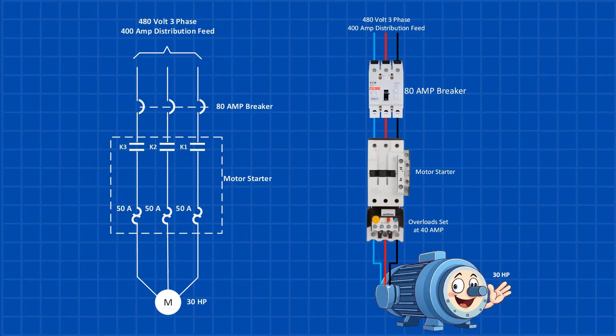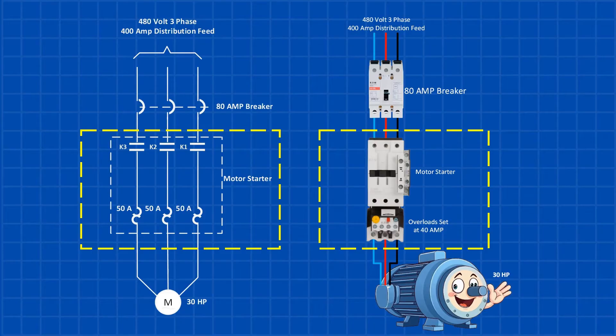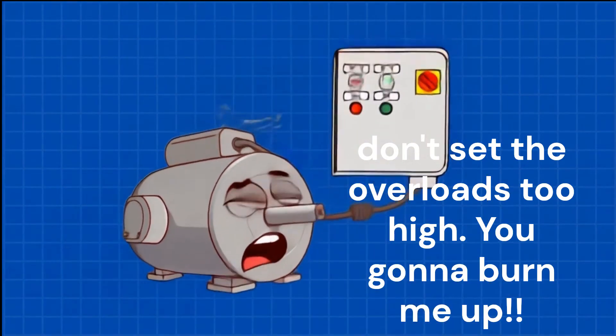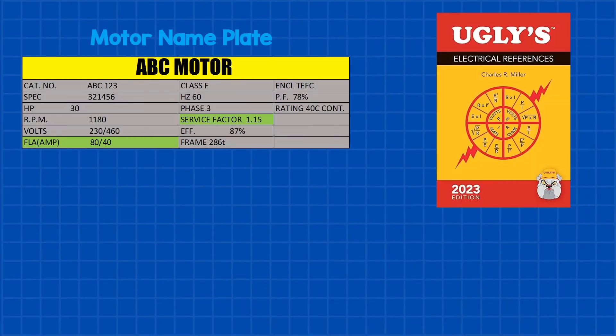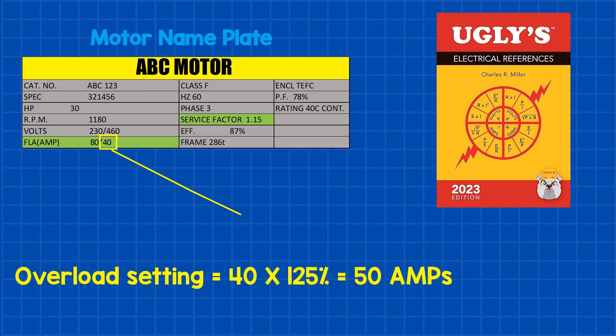To start a three-phase motor, all three phases need to be powered simultaneously, and that's where a motor starter comes into play. It has three contacts that close at the same time to send power to the motor. The motor starter also includes overload protection. If the motor draws too much current beyond the set limit, the overload protection trips, cutting off power to prevent motor damage. The overload setting should never exceed 125% of the motor's full-load current. For a 30-horsepower motor, this means the setting should be no higher than 50 amps.